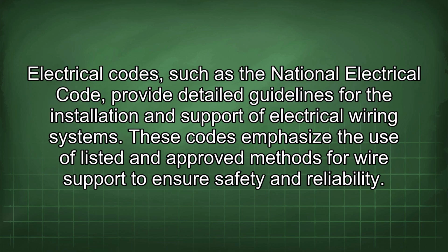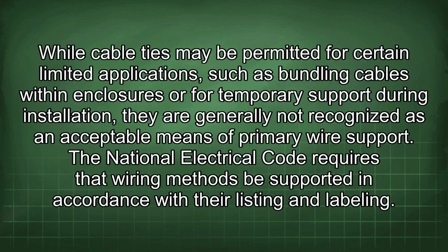Electrical codes, such as the National Electrical Code, provide detailed guidelines for the installation and support of electrical wiring systems. These codes emphasize the use of listed and approved methods for wire support to ensure safety and reliability. While cable ties may be permitted for certain limited applications, such as bundling cables within enclosures or for temporary support during installation, they are generally not recognized as an acceptable means of primary wire support.